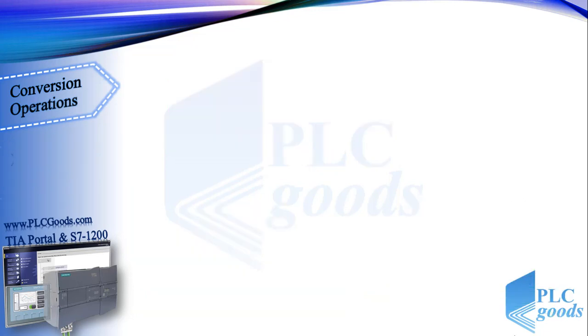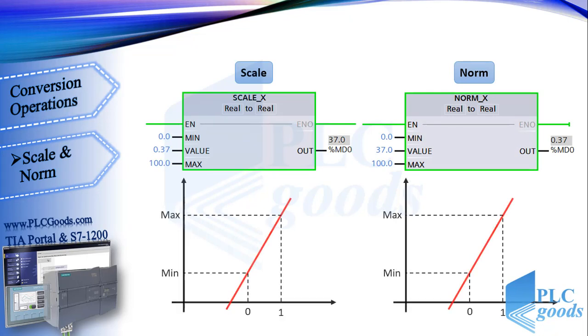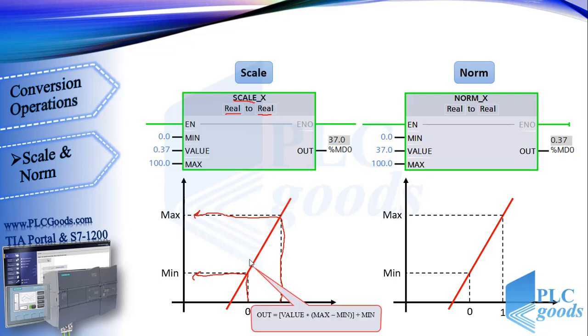The Scale and Norm instructions are used to change a specified range with a linear relationship. First we must determine the input and output data types. These instructions have three inputs. By the Scale instruction, 0 goes to the minimum value and 1 goes to the maximum value. With two points we can write a mathematical function to represent the linear relationship.